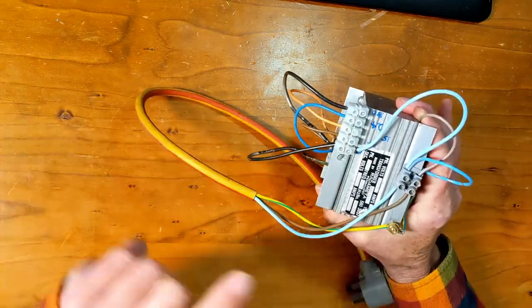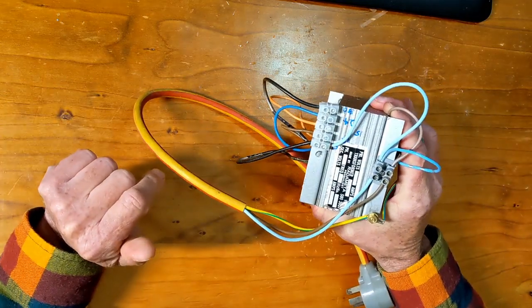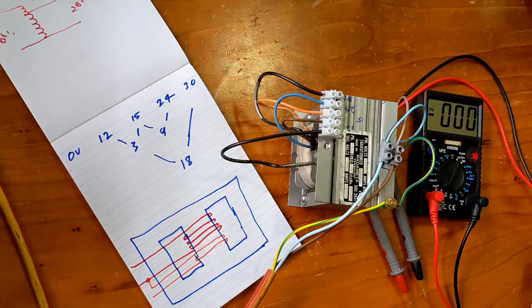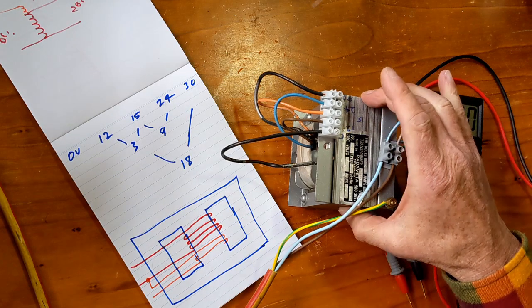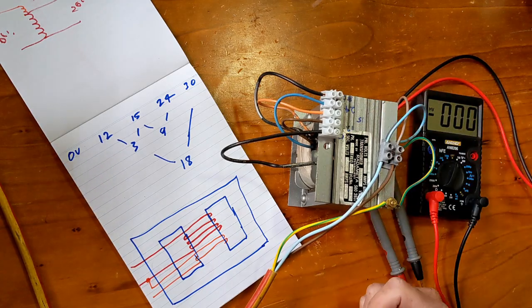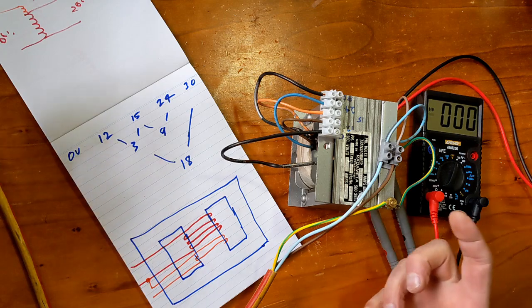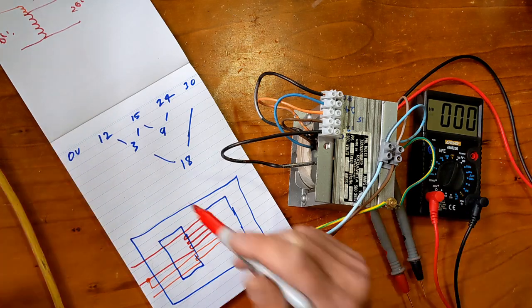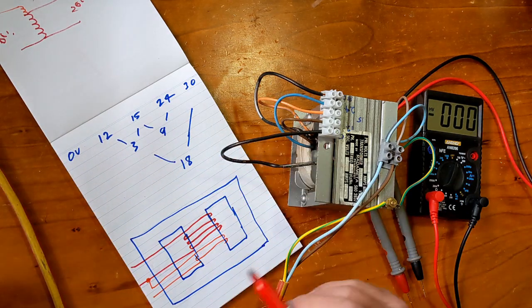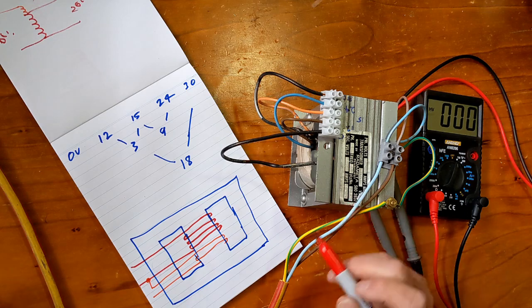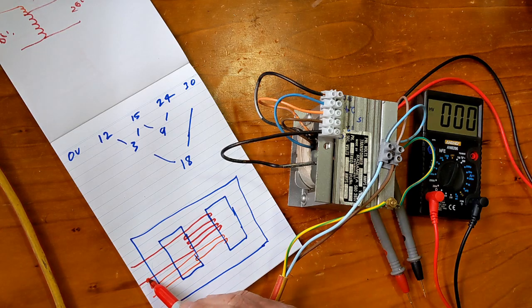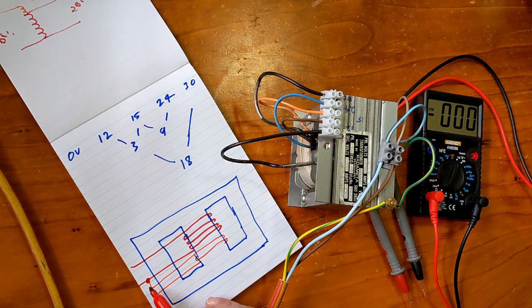Today I'm going to turn this transformer into an autotransformer. Now an autotransformer only has one winding. I know that this transformer has two windings, but I'm going to connect the secondary winding in series with the primary winding. If you want to know about the rest of these numbers, you can go back and see my last video. So what I'm going to do is connect one leg of the secondary to one leg of the primary, and then I'm going to connect a load across.